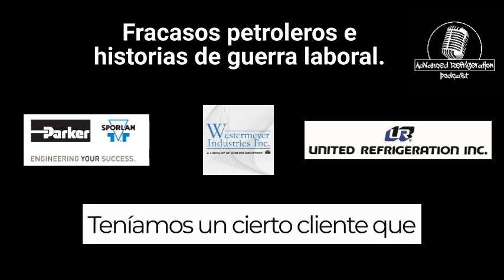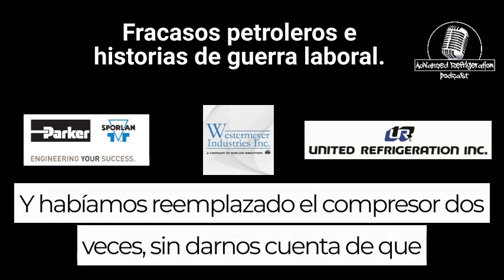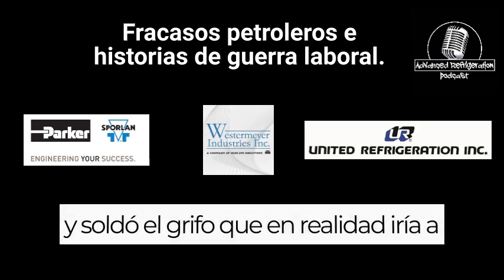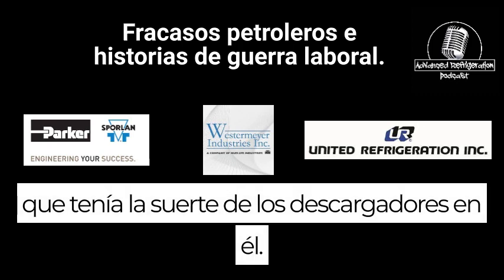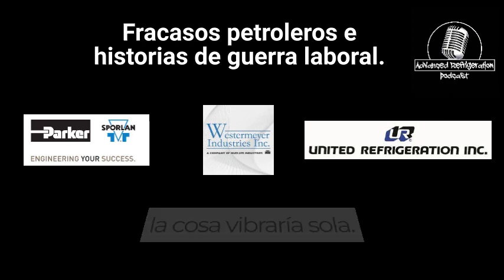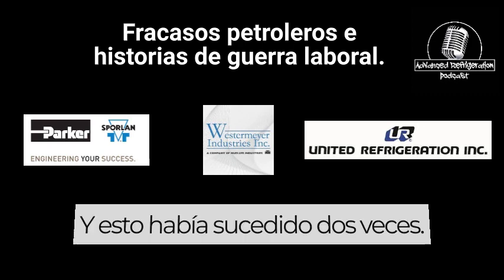We had a certain customer whose stores we had just taken over. They had a Carlyle compressor and we had replaced the compressor twice, not realizing that the contractor before us had actually cut off and welded off the tap that would go to the oil equalization line for this one compressor. This compressor was the primary, the one with a lot of the unloaders on it. It would fill up with oil, and we would break rods and the piston, and the thing would vibrate itself apart. And this had happened twice.